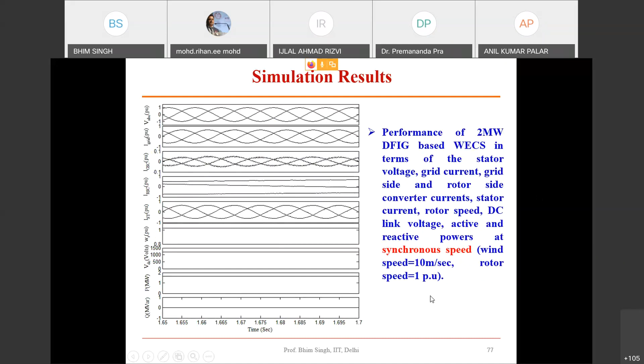This operates typically at synchronous speed, but can work over a wide range of speeds. That's the example I wanted to explain: if you operate a 2 megawatt wind turbine with a 2 megawatt DFIG versus using the 2 megawatt wind turbine with a 1.5 megawatt DFIG, how the losses and efficiency are affected.